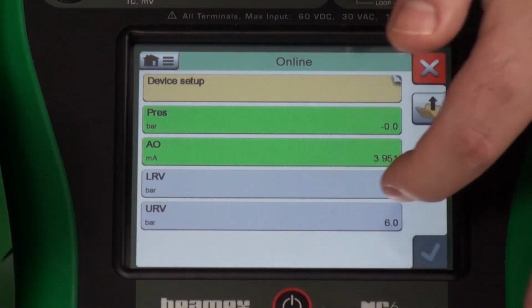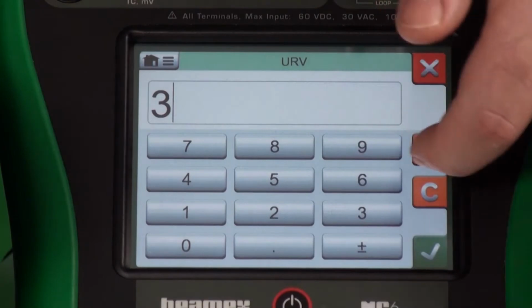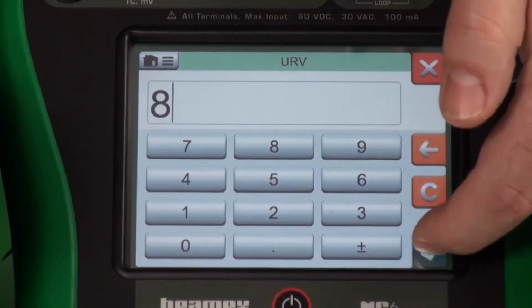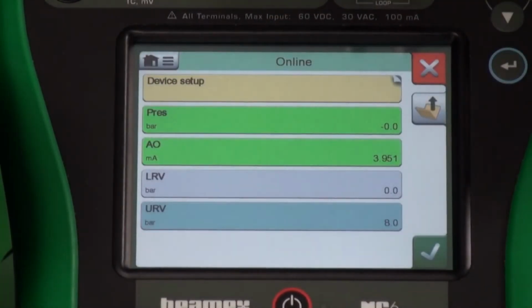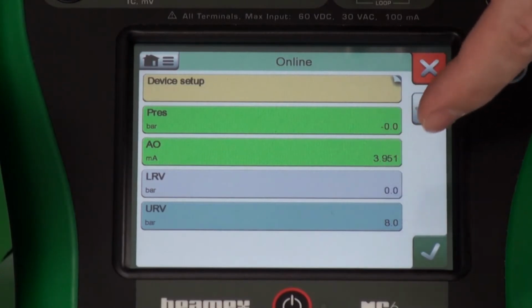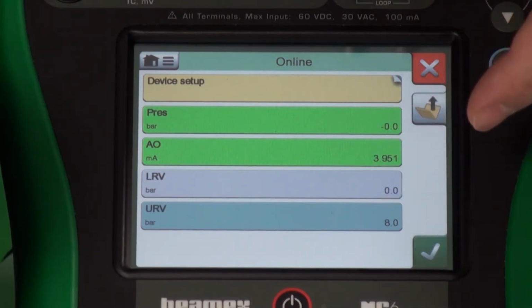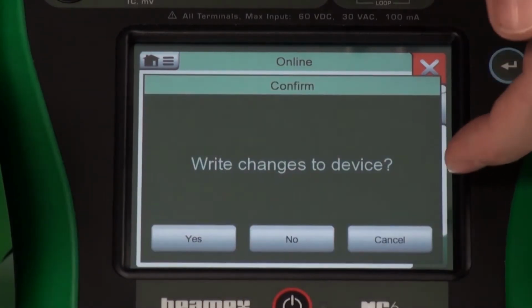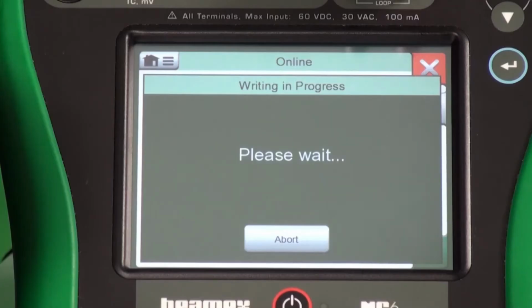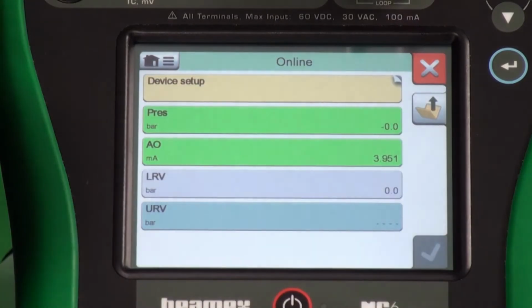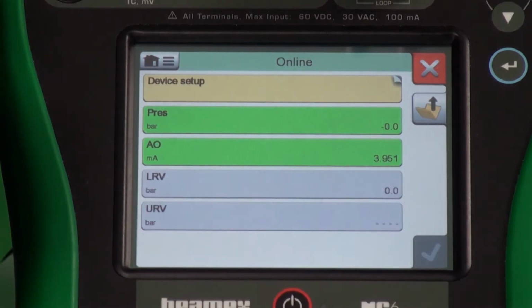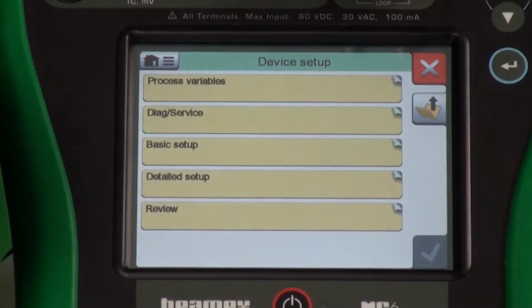You know what? Let's make this 0 to 8 bar. Now it's changed to blue. That means that there is a change ready to be written. So if I hit check, write changes to the device, yes. So now we're communicating back to the device. We're changing it physically to a 0 to 8 bar transmitter. And that's complete. You have access through setup to the other functions as well.